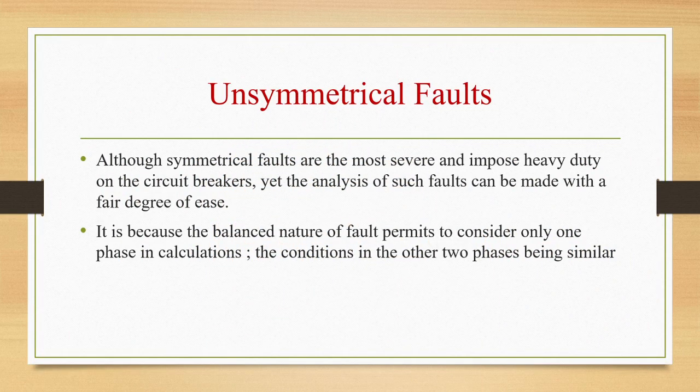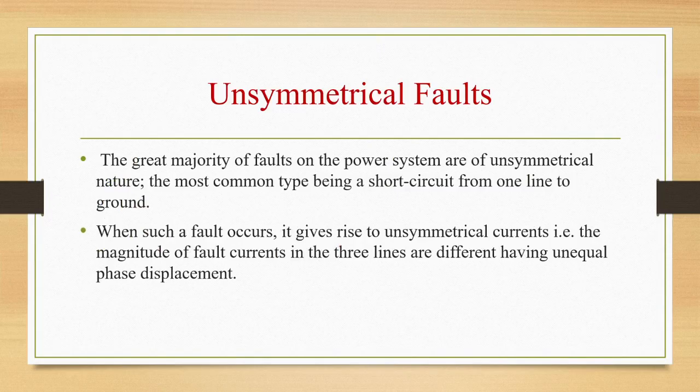Although symmetrical faults are the most severe and impose heavy duty on the circuit breakers, yet the analysis of such faults can be made with a fair degree of ease. It is because the balanced nature of the fault will permit us to consider only one phase in calculations, the conditions in the other two phases being similar.